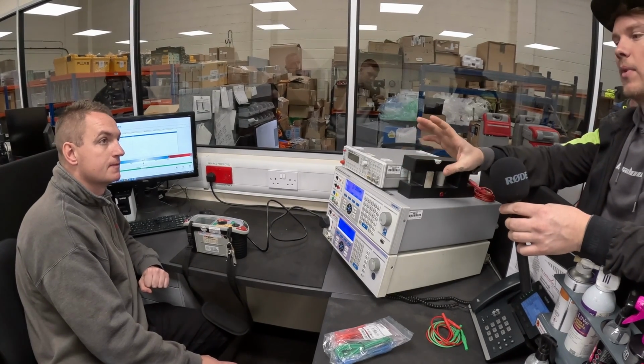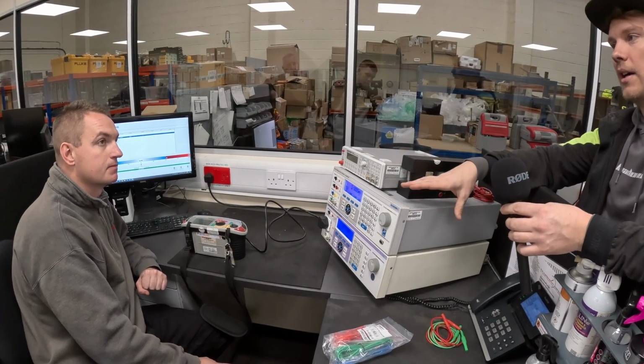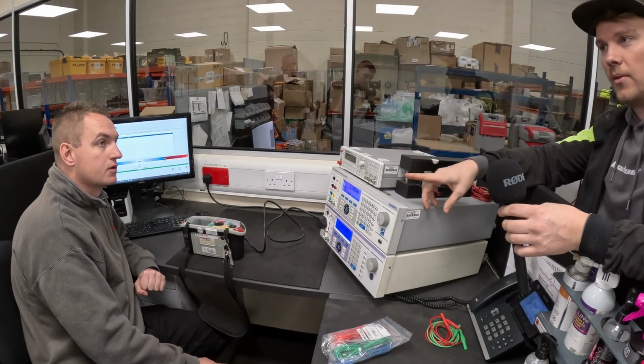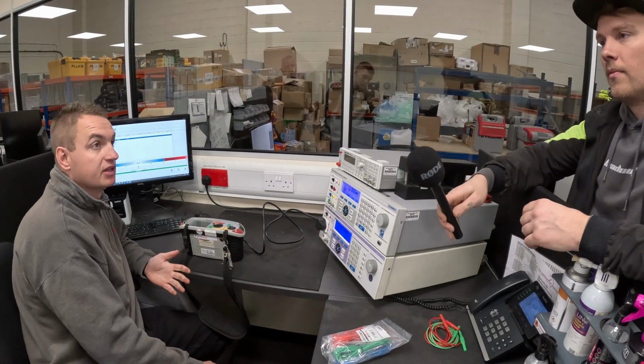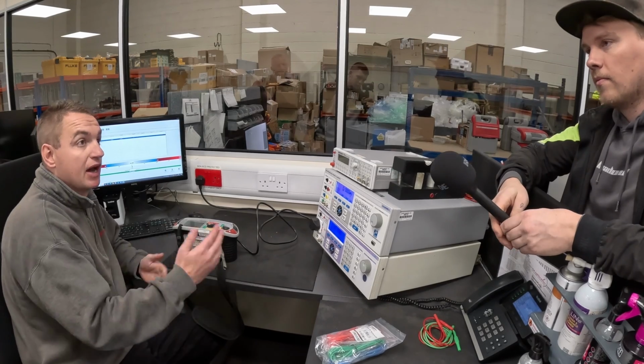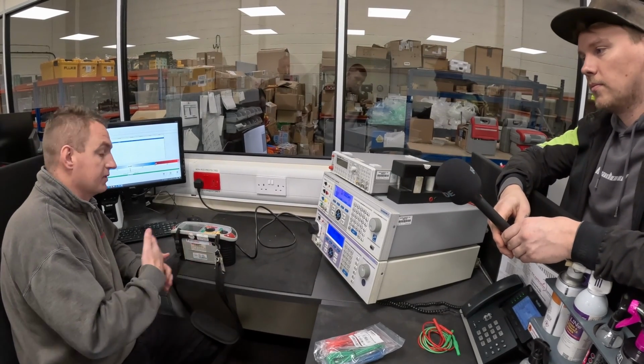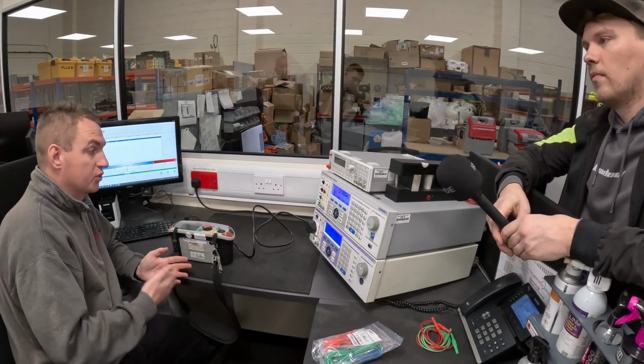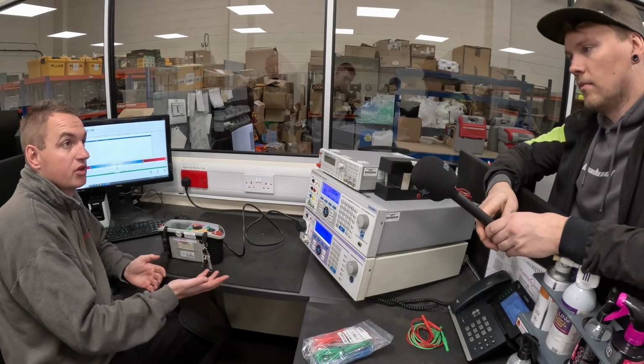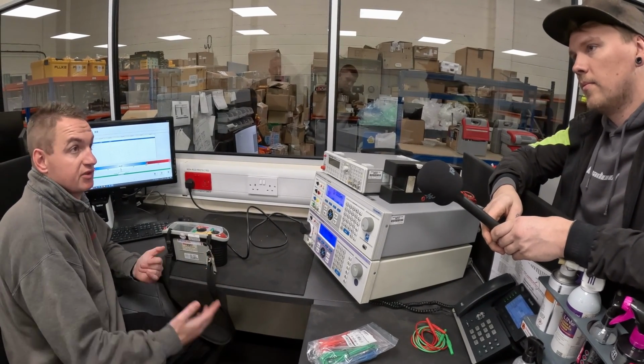What happens if it's out of the limits? If it's too high, do you then start having to take this apart? No, basically we would then contact the customer to tell him that it's failed on a certain range. Then it's up to him whether he wants it repairing. We'll give him a fixed cost repair on the unit, and then it's just a yes or no to go ahead.